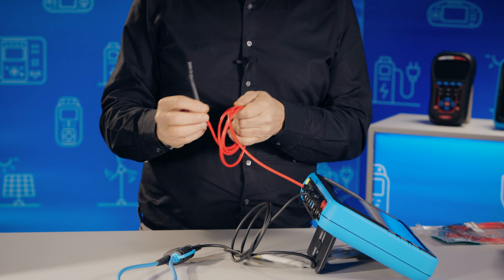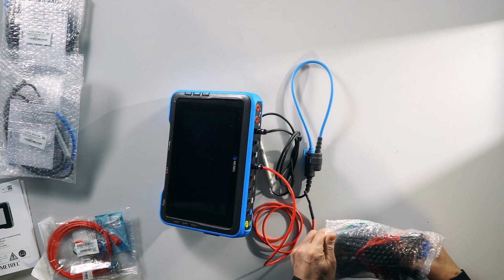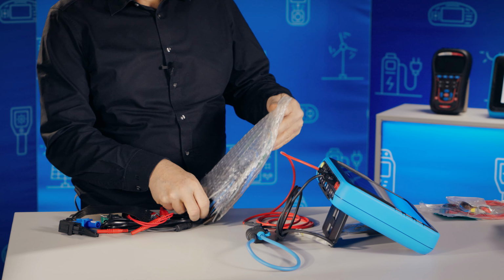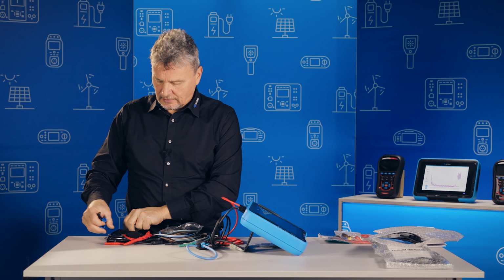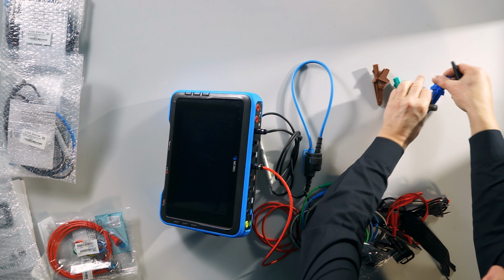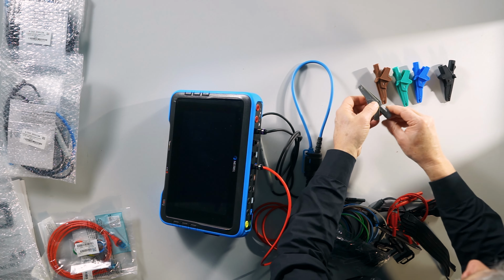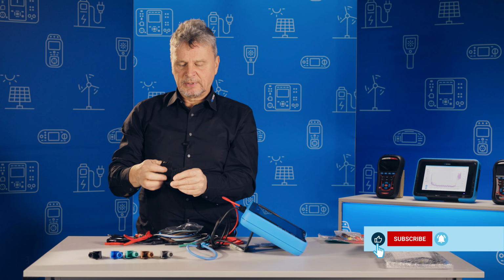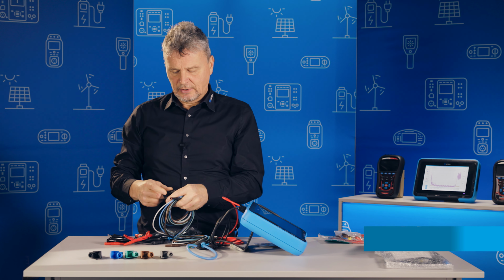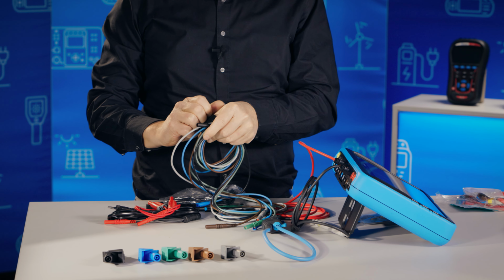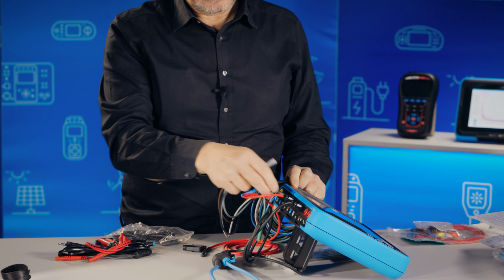Let's check what kind of voltage test leads we are delivering with the set. Inside this huge pack there are a lot of different accessories. So we have 5 crocodiles for voltage input. Then we have a special hook where you can attach all the test leads together, so as to have good orientation in the box. Then we have 5 voltage test leads, which are intended for connecting voltage phases 1 to 3, neutral and ground. They are color coded, so gray should go to gray, brown to brown, and so on.